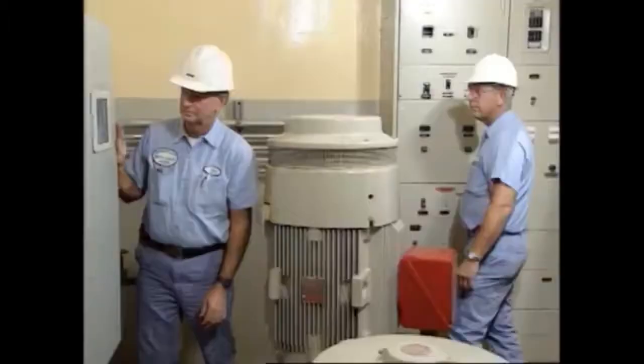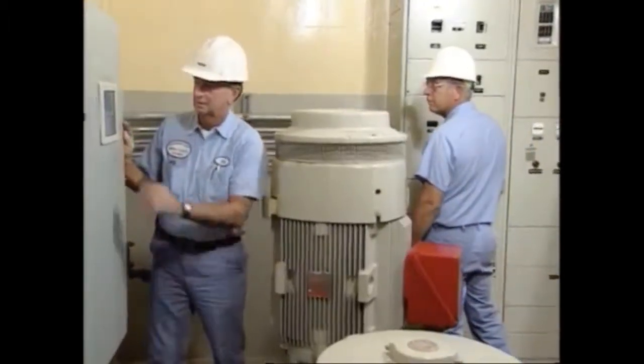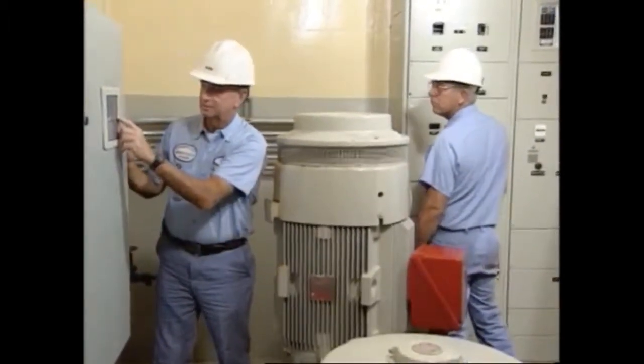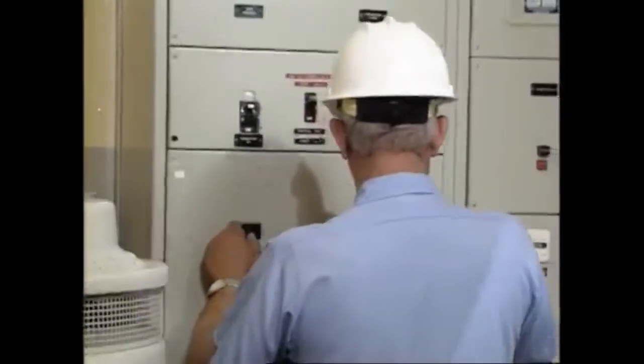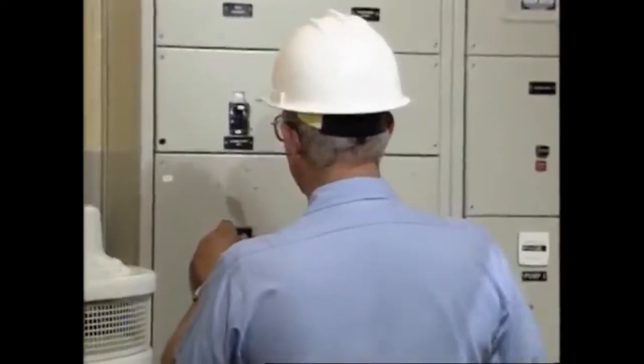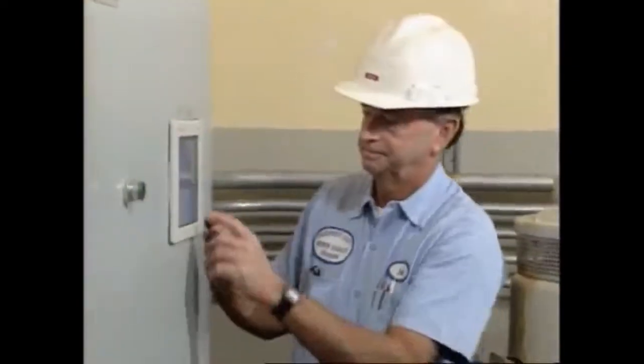What is the critical period of time if the station does fail? When this critical time is determined, it tells the station crew how long they have to respond to an alarm condition before backup flooding or overflow will occur.